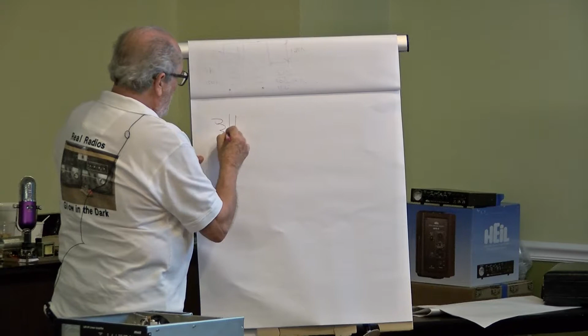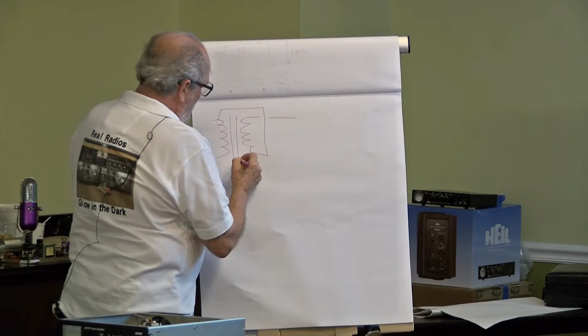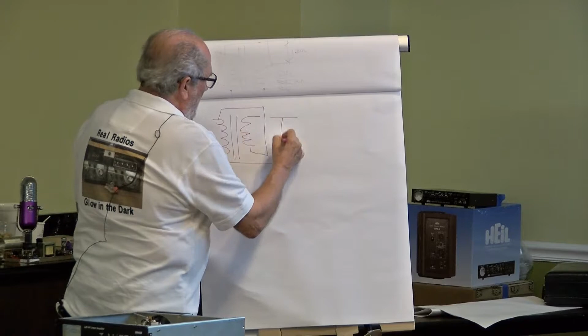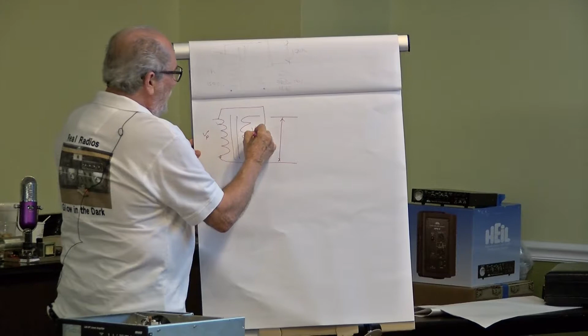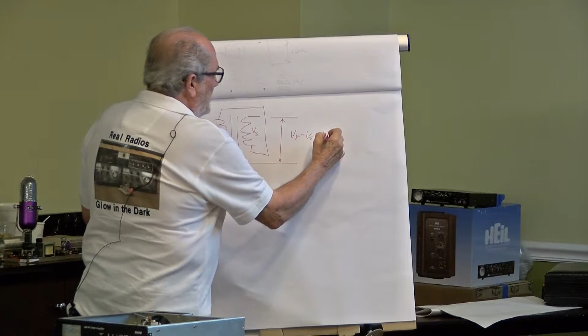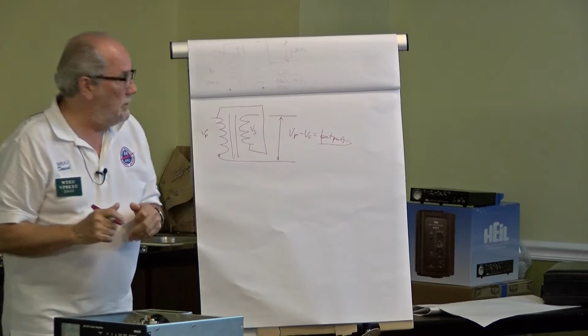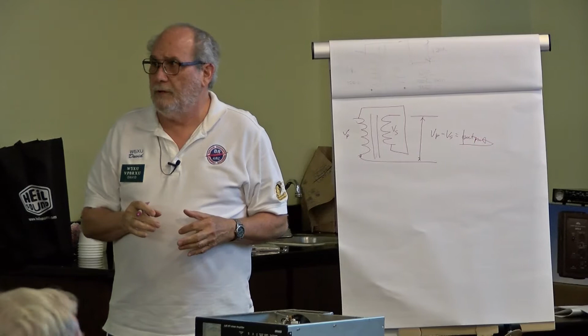So what happens if I take the connections and take advantage of this phasing in the transformer? Let's redraw our transformer, and I do this, and take my voltage from here to here. Then it's the primary voltage minus the secondary voltage that gives us the output, because the connections are out of phase. That's called a buck transformer—I'm taking whatever voltage is on the secondary and using it to reduce the voltage on the primary.